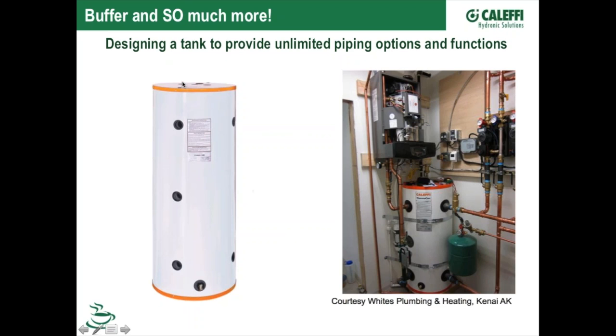It's a glass-coated tank, and the reason for that is, well, let's make it so if somebody wants to use it for domestic water storage, it can be a multiple-purpose tank. So we went with a glass-lined tank. You can put 2 anode rods in it. There are tappings at the top that you can drop a couple of anode rods in to make sure that you get a good life cycle out of that tank, by having the 2 sacrificial anode rods dropped into that. It's got a nice coated jacket and stuff like that.